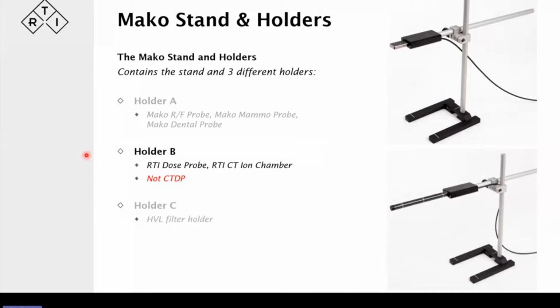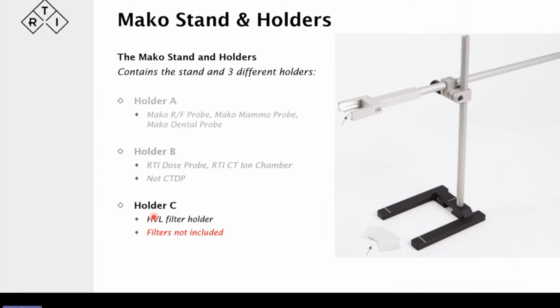Then there's the second holder, which works with the RTI dose probe and the CT ion chamber, like so. That may be used when you have applications to measure skin dose at a certain distance, or for CTDI free in air, as for those applications. And then the last one, dose holder C, is for HVL filters. So you have a filter pack, and they fit into the holder nicely.